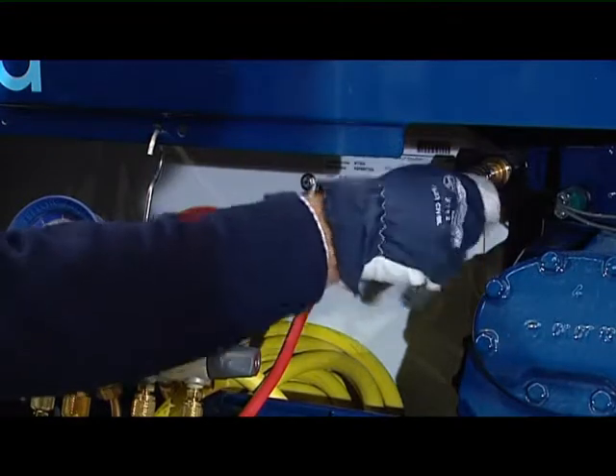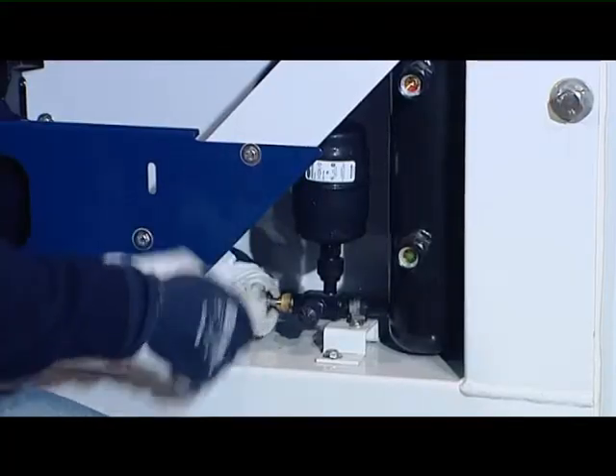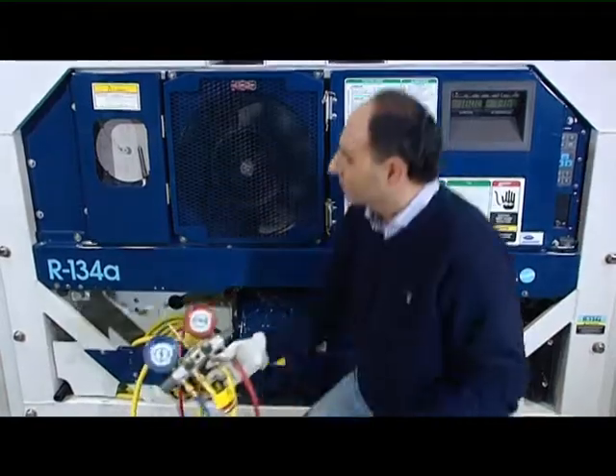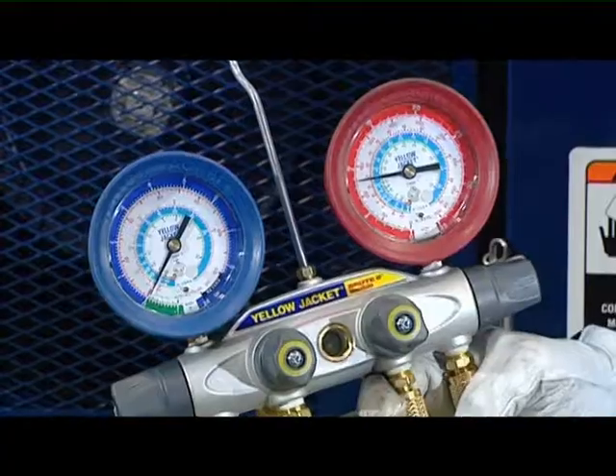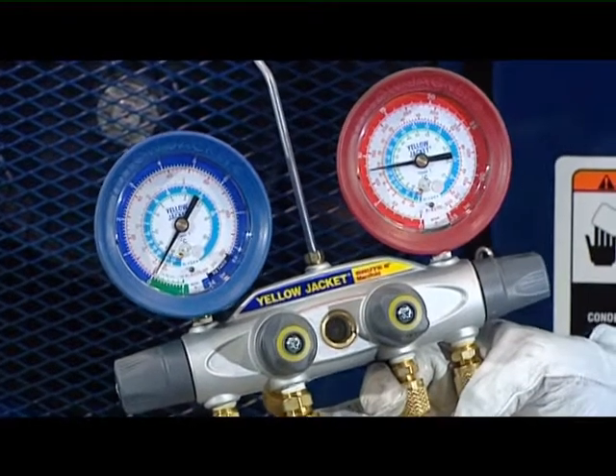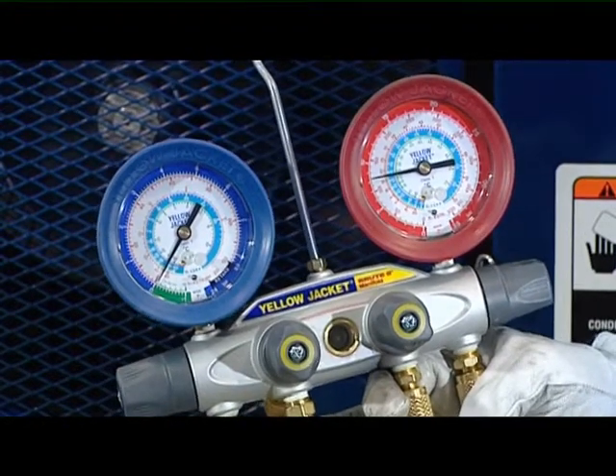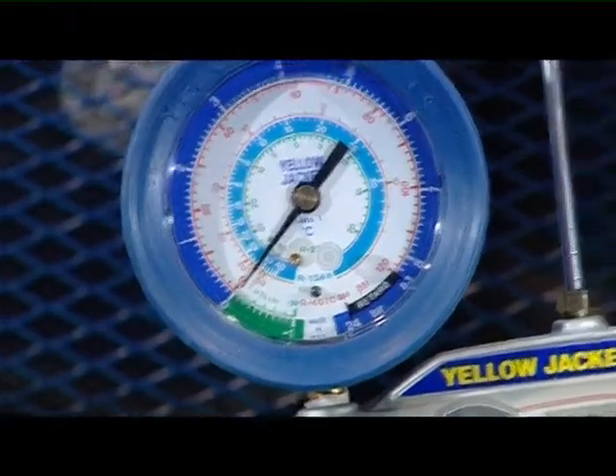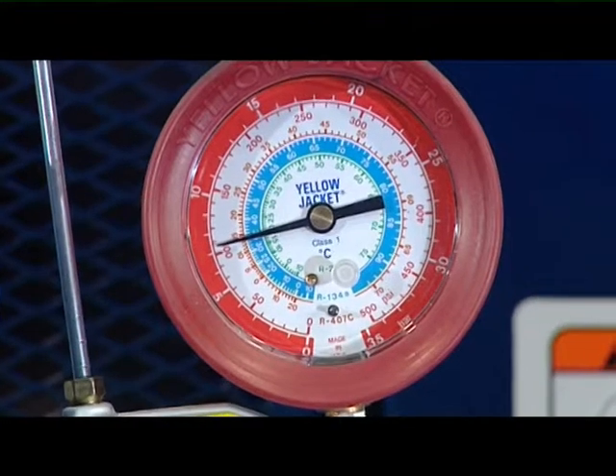Open the discharge valve of the compressor and place the king valve in the back-seated position. Switch the unit on and check if the pressures are all right. To remove the gauge manifold set, see the Checking Compressor Pressures section.